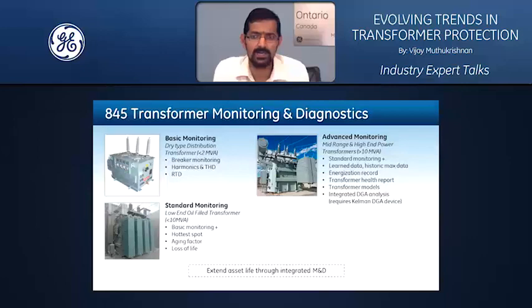Transformer models. Here is a group of functionalities that are brought into 845 in an integrated way. We have a portfolio of dissolved gas analyzers within GE, an approach of online monitoring of transformers using dissolved gas analyzers. The offering we have on 845 is an integrated solution that brings both the electrical characteristics and the chemical characteristics together, and gives you analytics built on the combined power of looking at the transformer in a holistic manner, and gives you intelligence that tells you what is wrong in a transformer.